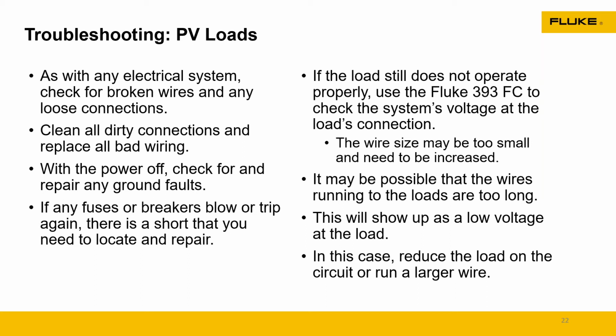When I was out in Oregon, they were having fault conditions happening. The load was having an issue. They did all of their investigation, determined that everything was working great from the solar panels all the way to the inverter. But after it left the inverter going to the step-up transformer, it kept tripping out. So once we did some investigation, we took a high voltage insulation tester, ran out there and started doing some testing. Come to find out, when they buried the three-phase line going from the inverter to the step-up transformer, they nicked the line. When it got hot enough, got enough current running across it, it shorted out and caused the inverter to trip and didn't get anything to the transformer.